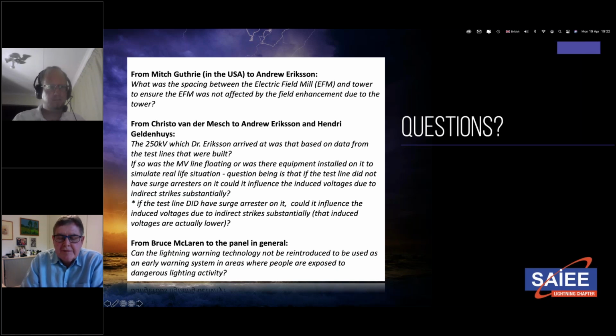Shall I go straight on to the next one? Yes, please, you can read. The test line was not floating, it was a practical line. It was energized. There were transformers on it, a generator providing the power. At various stages of the project, there were surge arresters on it, and the currents were measured at the base of the surge arresters. In Henry's stage of the project, which went much further, a number of practical applications were investigated.